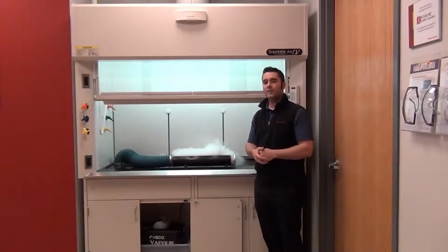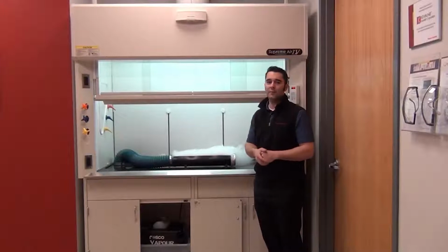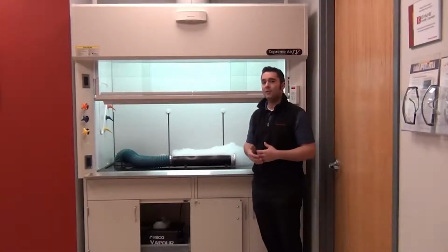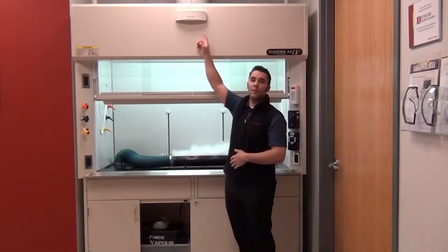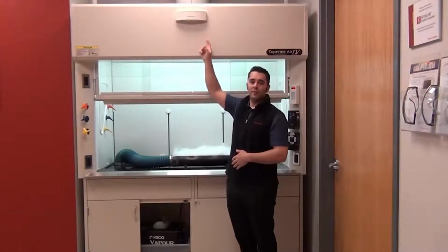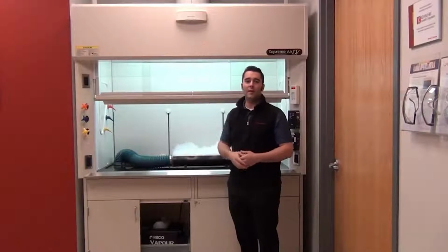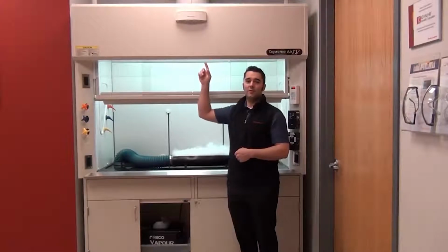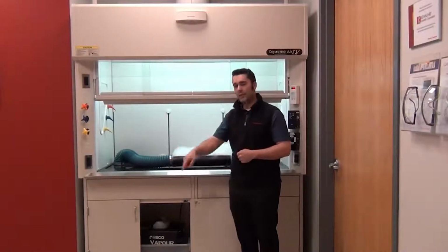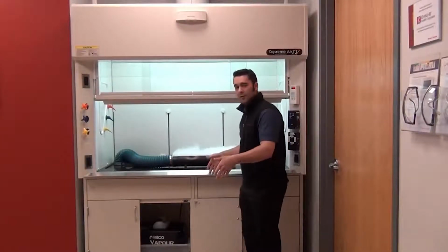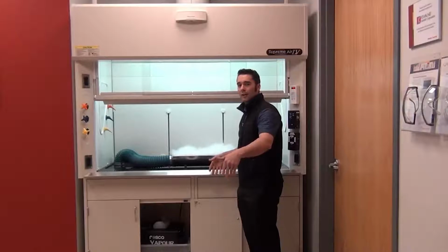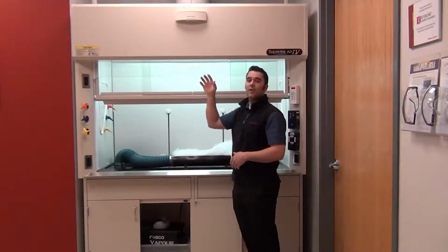So at Phoenix Controls, we have designed some smart controls called usage-based controls, which allow a fume hood to set back to a lower airflow when nobody is present, even if the sash is left open. Now we call it a zone presence sensor. It is not strictly a motion sensor like you would think with most other products. The Phoenix Controls zone presence sensor, which I'm pointing to here, actually has an imaging chip built into it and an infrared generator. So it is not looking at Doppler shift radar technology like you would see with most other motion sensors.